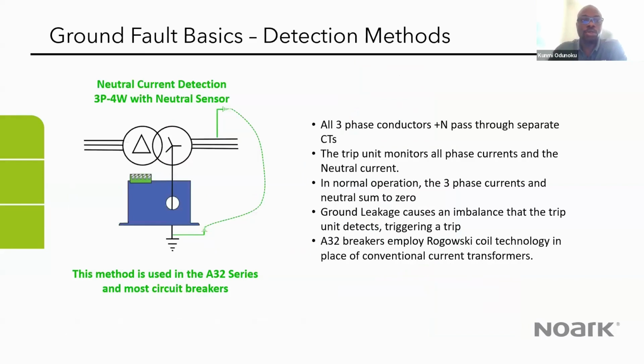And then we have also the ground fault protection. For our breaker, we have a neutral current detection sensor, which is an external device. We use the Rogowski coil, and we also have the solid bar. What that does is monitor the current through the neutral leg and also the 3 phases passing through the breaker. And once the sum is not equal to 0, it means that there is a leak somewhere. This will trigger a trip for the circuit breaker.